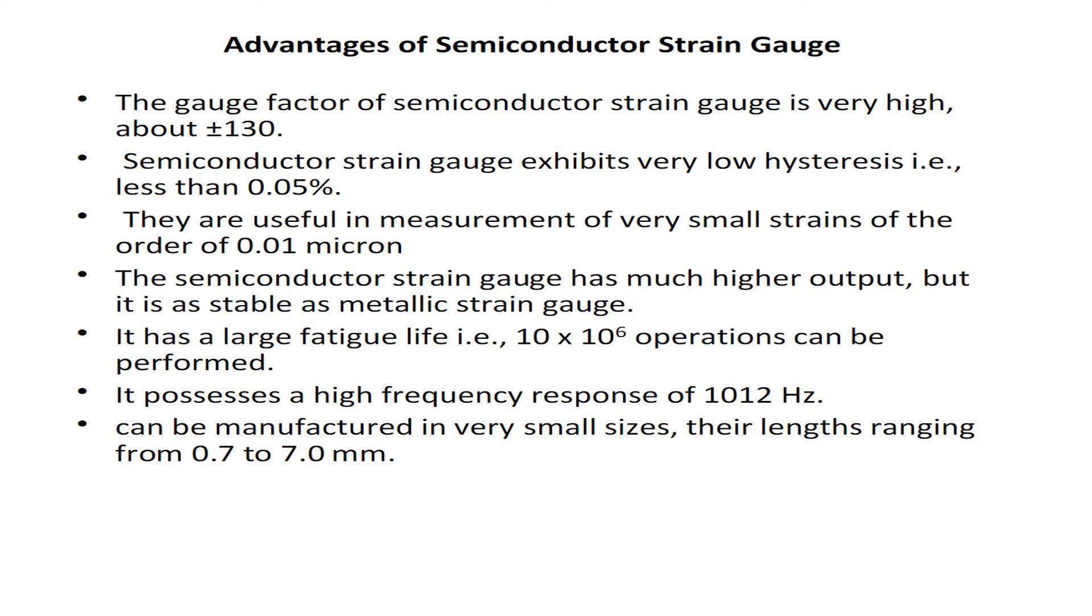Advantages of semiconductor strain gauges: The gauge factor of semiconductor strain gauges is very high, about ±130. Semiconductor strain gauges exhibit very low hysteresis, less than 0.05%. They are useful in measurement of very small strains of the order of 0.01 micron.